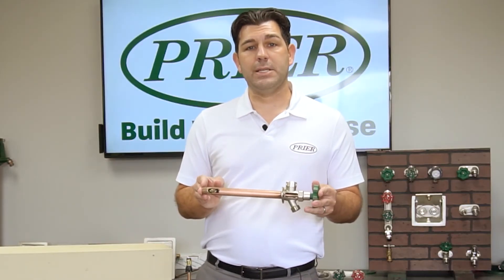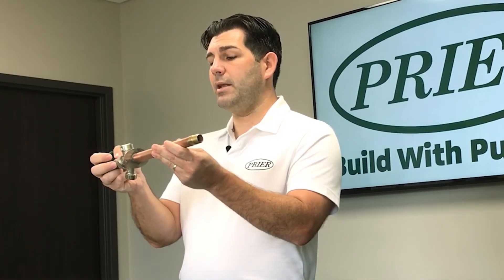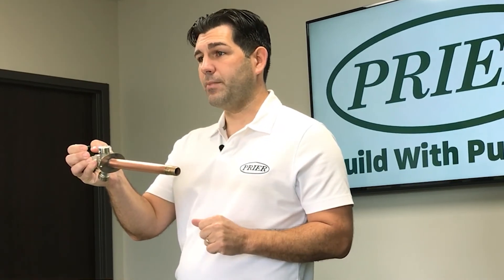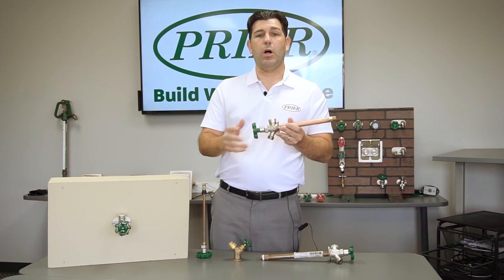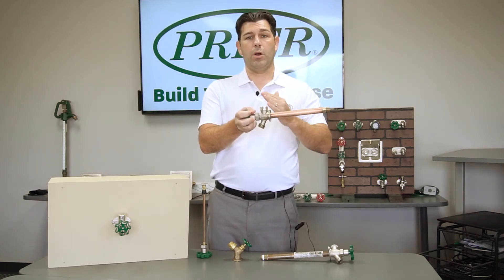The first thing that can cause these not to drain properly is if they are installed wrong. When you install your valve, if you do not give it a downward pitch to allow the water to leave the system — if it is set a little bit upward — gravity will keep the water in the pipe where it can freeze, expand, and rupture. All Prier valves actually come with a pitch built into the flange, so once you mount it to the building, it will automatically pitch itself to give you the downgrade, allowing water to leave the system.